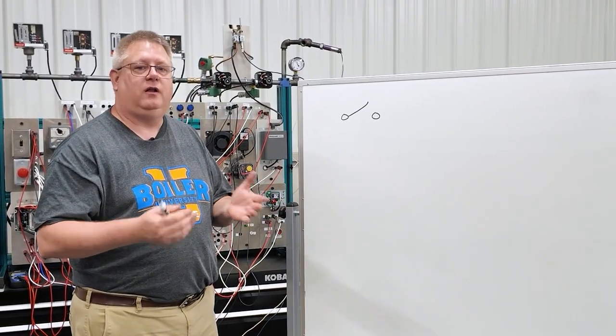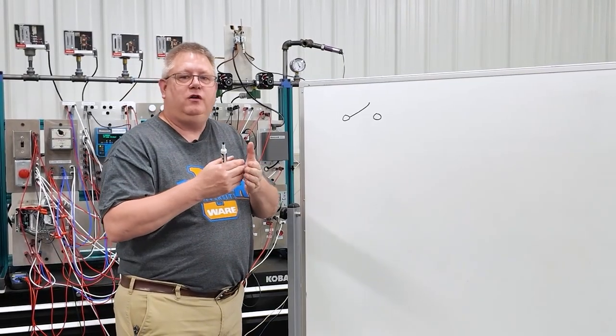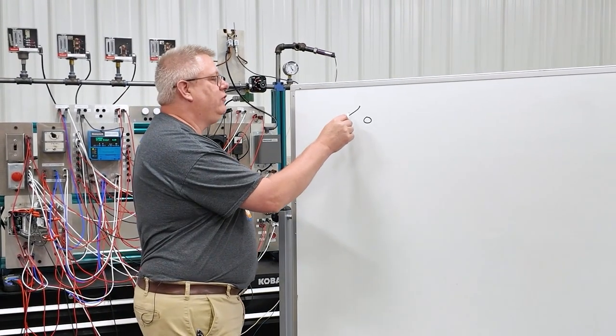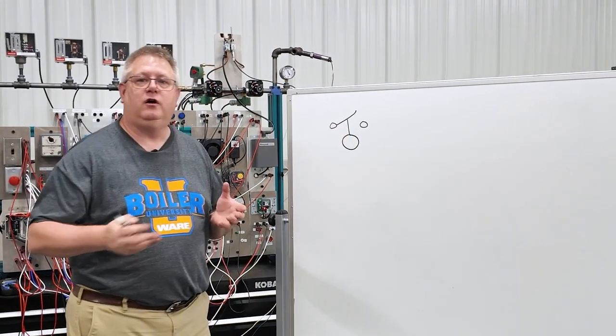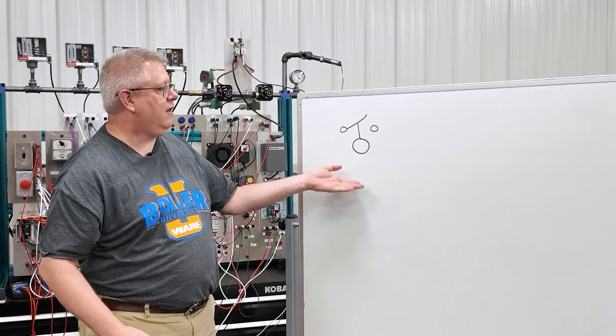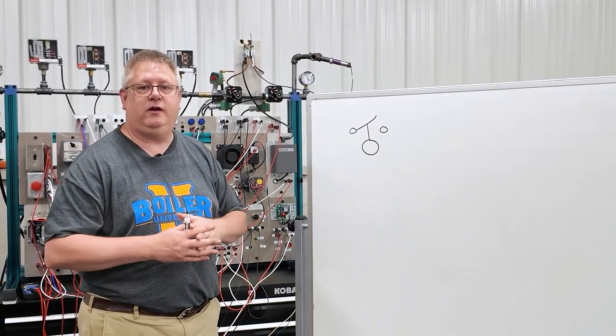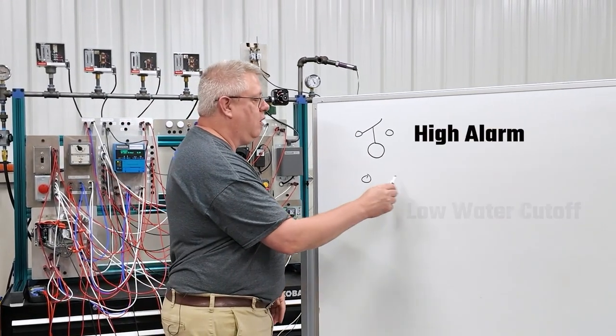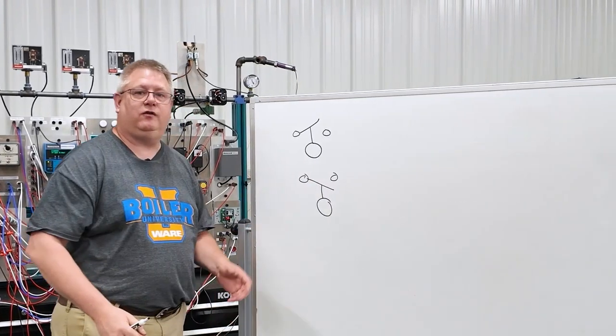If we've got a switch like our first low water cutoff switch, generally those are floats. And we can illustrate that on a diagram by having a round float shape. So if you think about a float ball, when the water level comes up, it breaks or makes the switch depending on whether it's a high alarm like I've drawn here or a low water cutoff with the float rising to make the switch.